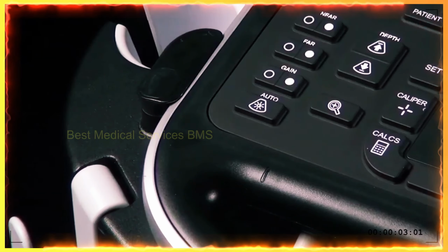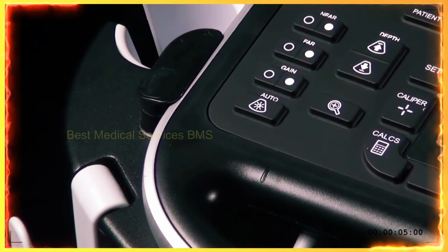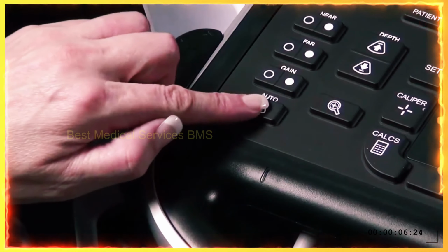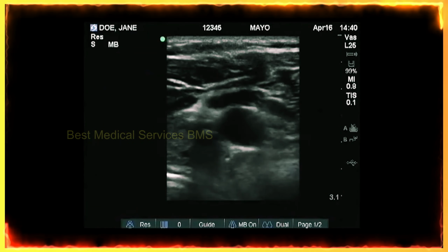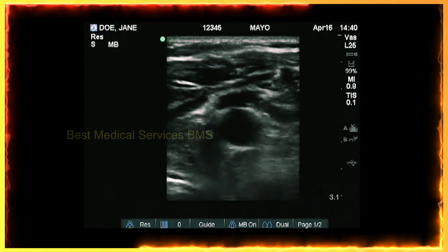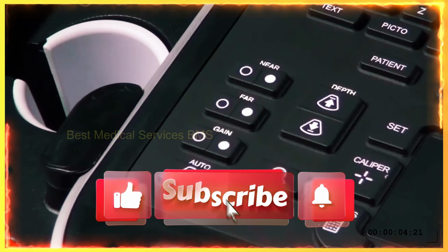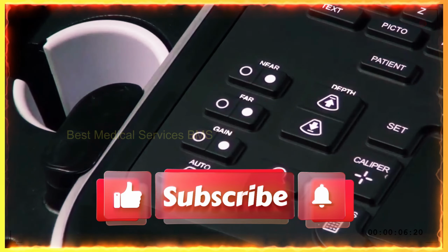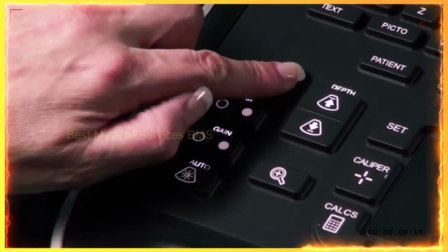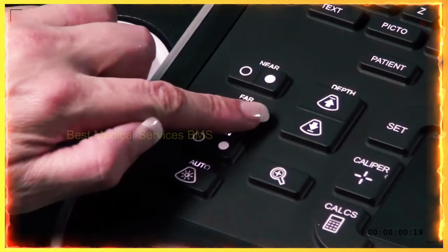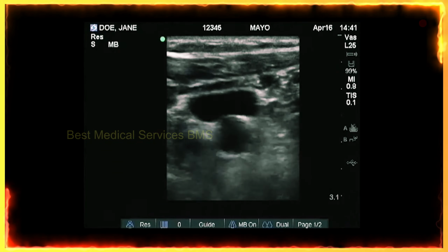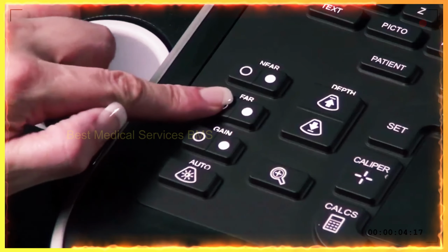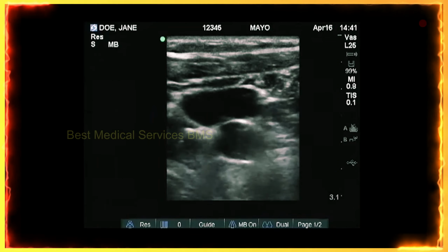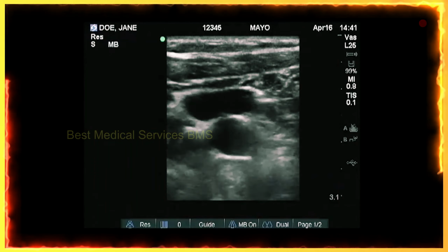For quick optimization of the gain settings on the system, press the Auto Gain key. The system will evaluate the image and apply the appropriate gain level settings to the image. If you would prefer to change the gain settings manually, adjust the near, far, or gain keys on the lower left side of the control panel to increase or decrease the amount of gain applied to the near field, far field, or the overall image.